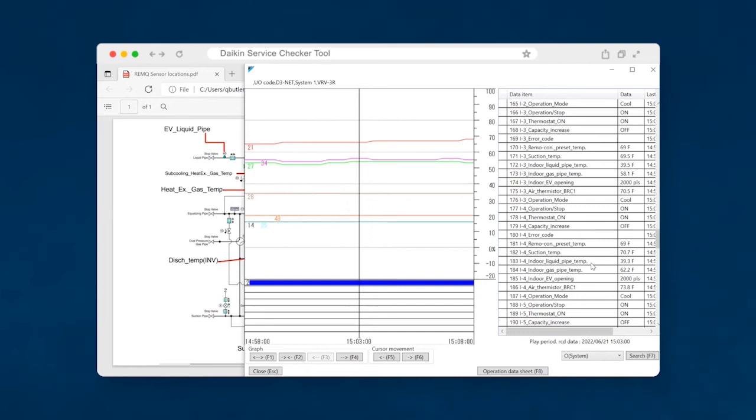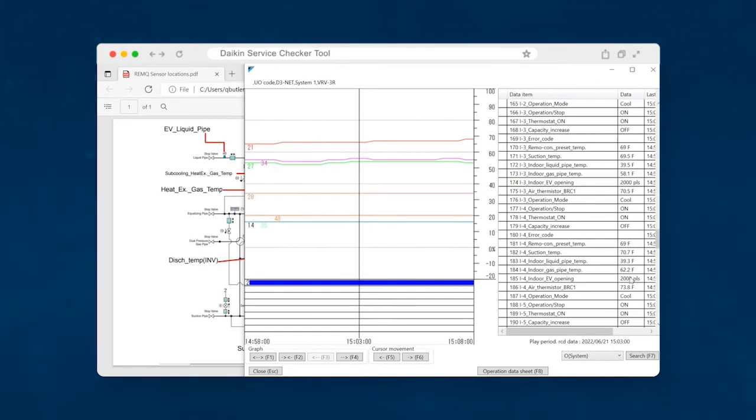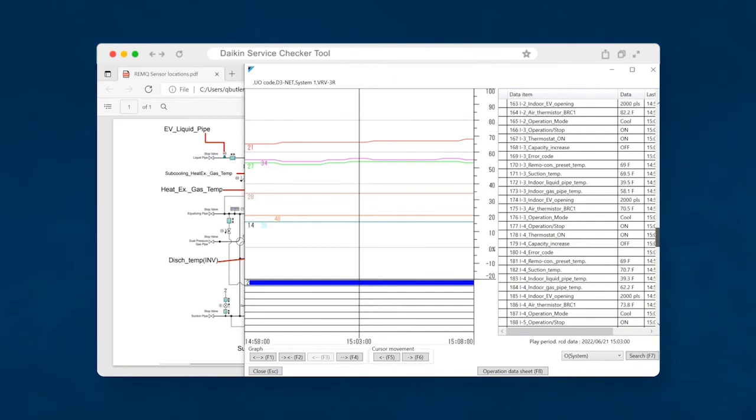So, under normal conditions, this will be a nine degree difference between these two and you should never see this indoor expansion valve above a thousand pulses under normal operating conditions. And so, once again, this is another point of, okay, this charge is definitely low on this system.